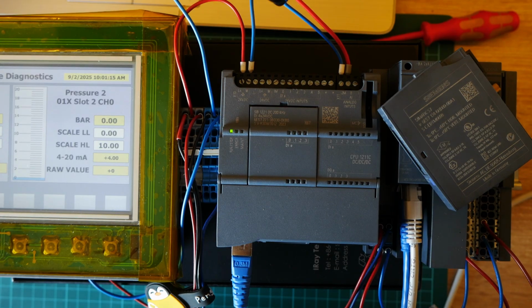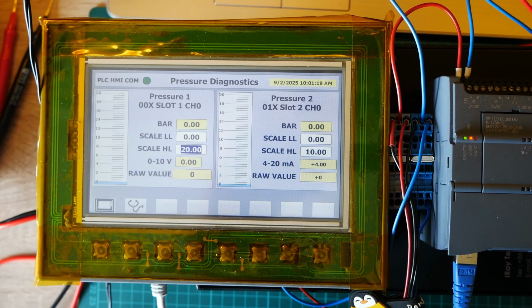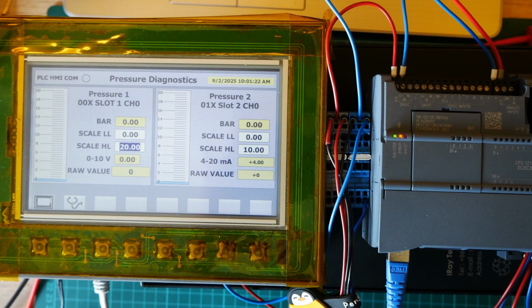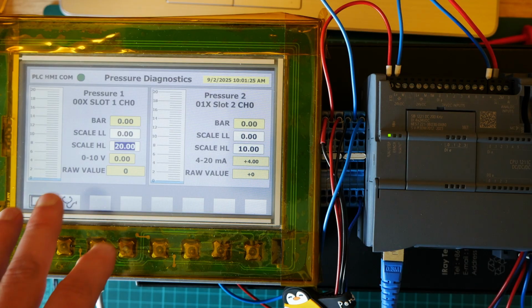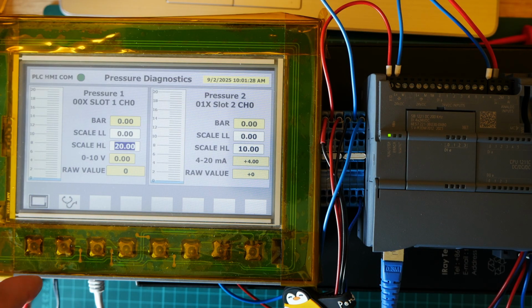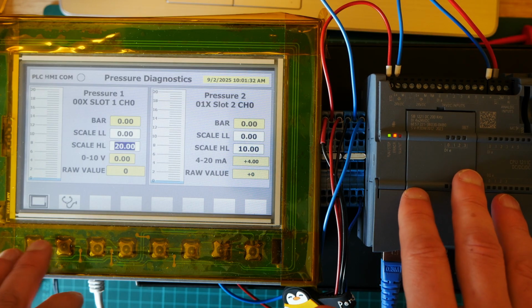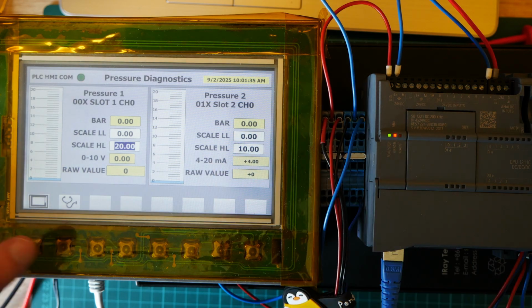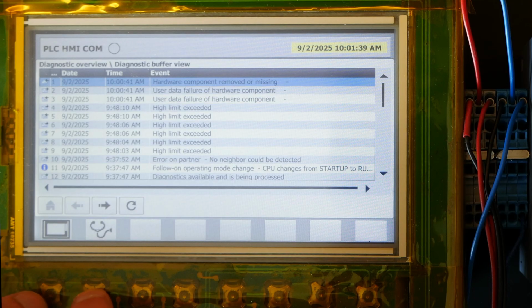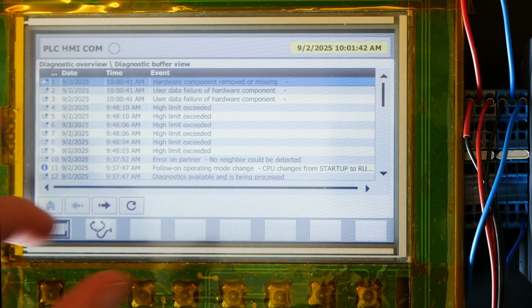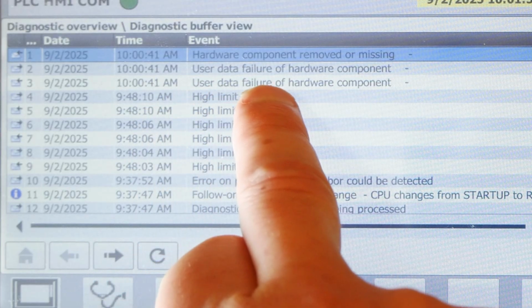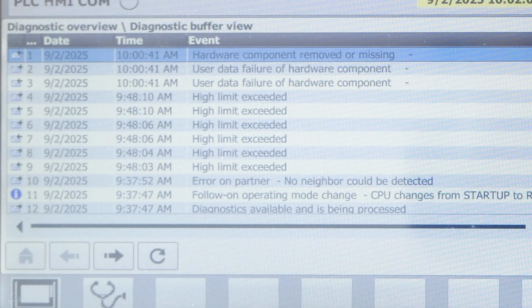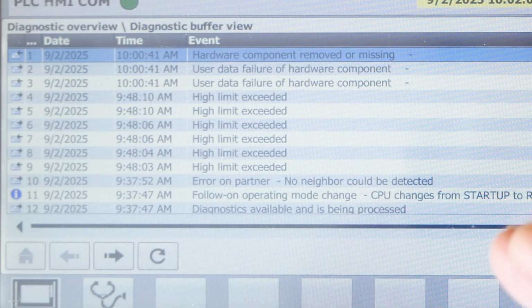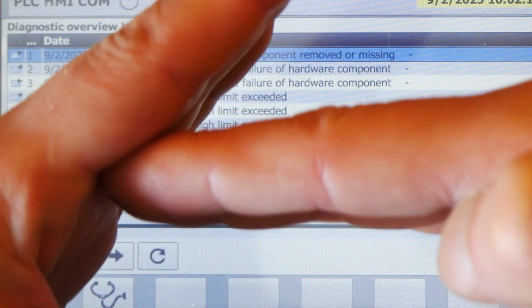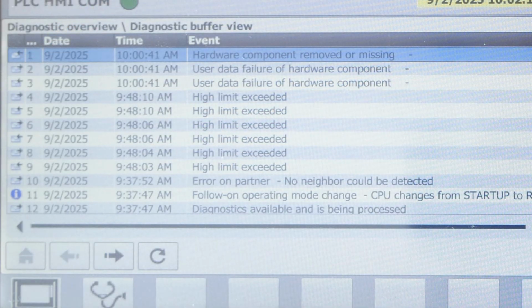also a very good tool to have in your HMI project. If you don't have that, you should probably ask to implement it. This is not alarms, but a kind of diagnostic buffer from the PLC. So a diagnostic view, not an alarm view, but a diagnostic view. Right now we will go to this diagnostic view, and what I see is the text hardware component removed or missing, and here is the arrow, this indication arrow goes to the left side. Okay, the arrow goes like that, so this means it is an incoming event.